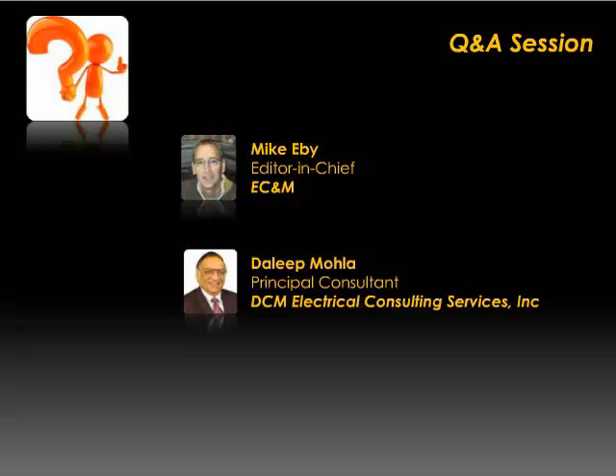If equipment is not properly installed and maintained, no time can be calculated. We do not have any technology to say, if you don't maintain the equipment, what the clearing time is going to be. Since the shock hazard effect and the flash hazard both depend on how fast the clearing time is, equipment should be properly installed and maintained. Again, my thanks for somebody who asked this question. Yeah, that's definitely a problem that needs to be addressed for sure.